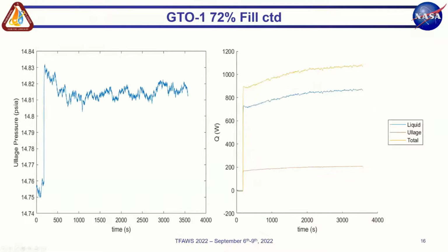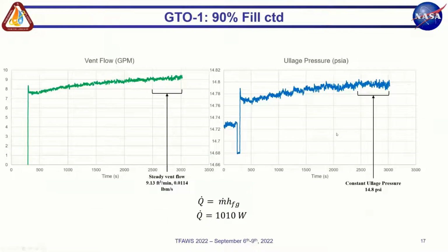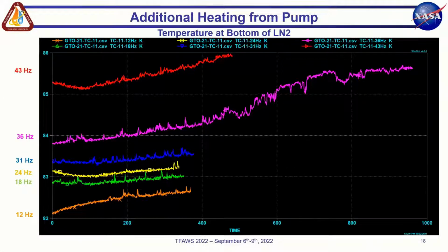So this is for the 72%. We did it also at 90%, and measured about 1,000 watts of heat coming in through this method. The next step was to characterize, we have our basic quiescent tank getting heating from the ambient environment, and we want to see what is the additional heat that comes when you start running the pump. So we ran the pump at a series of increasing speeds from 12 hertz all the way up to 43 hertz, and we were able to start picking up this heating trend as the testing went on.